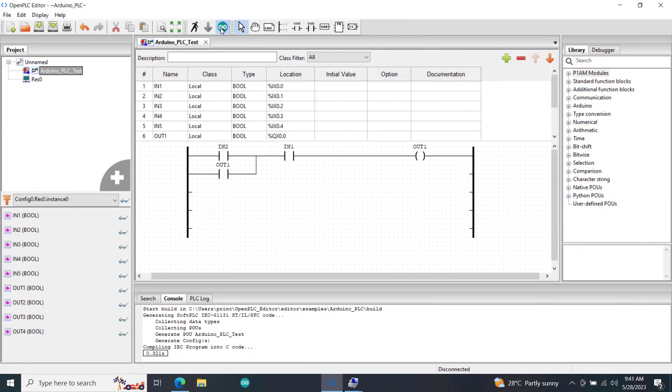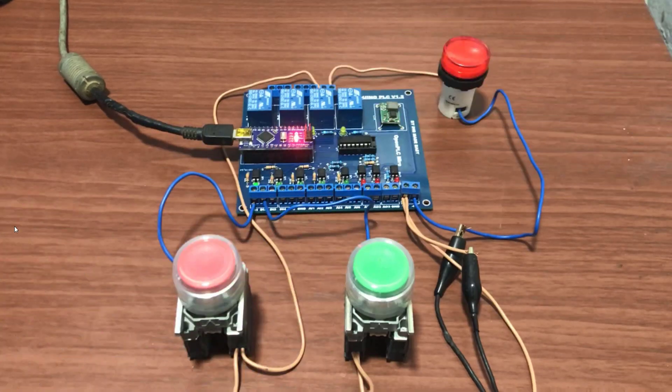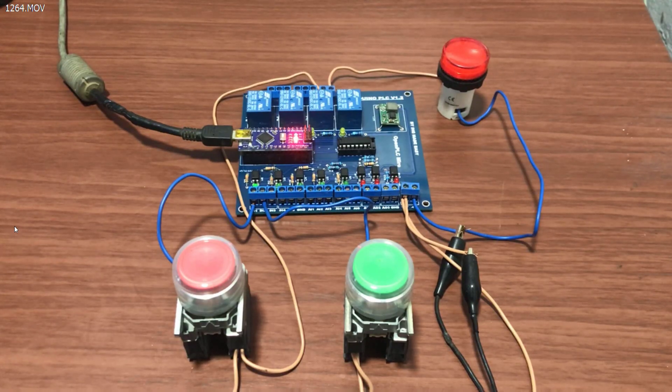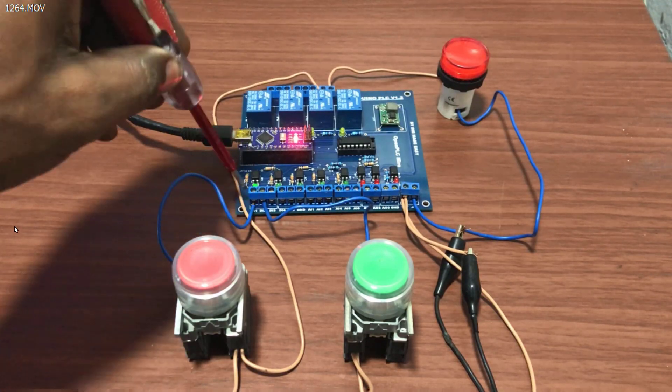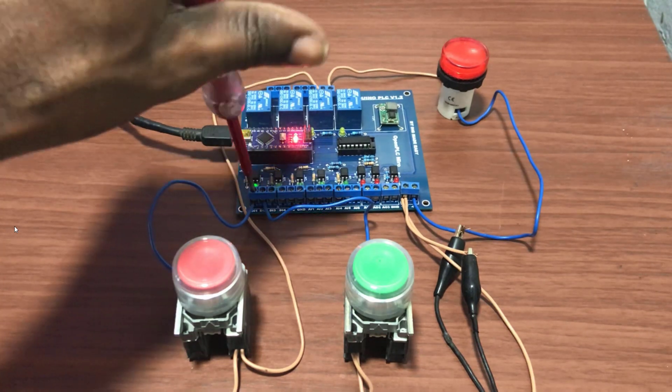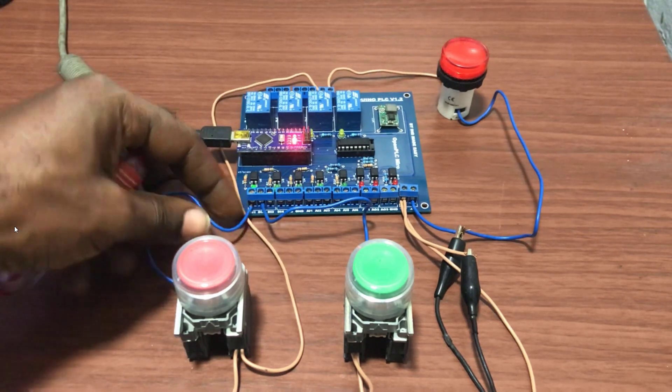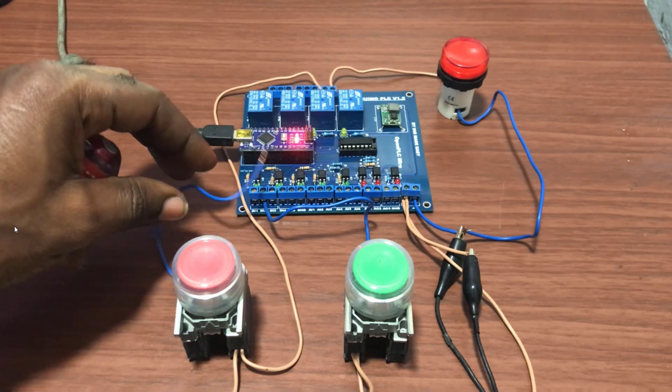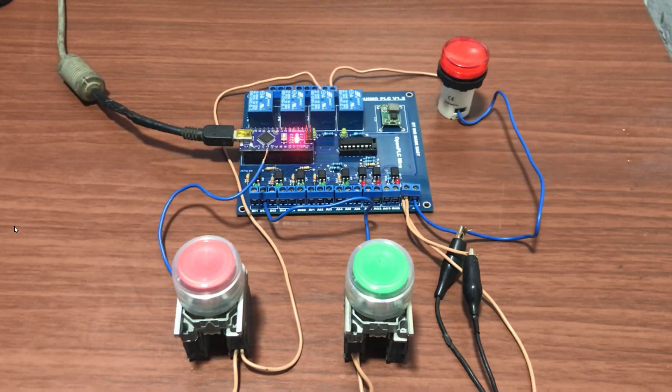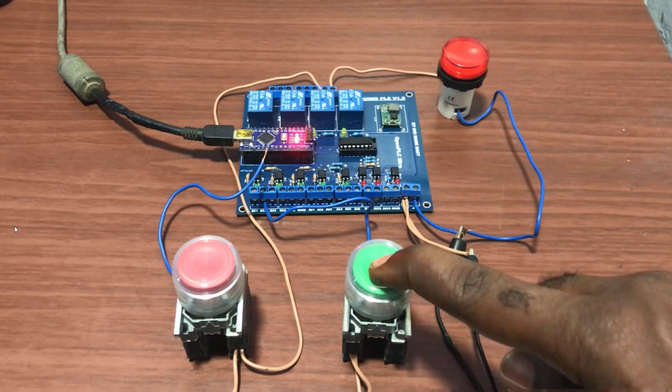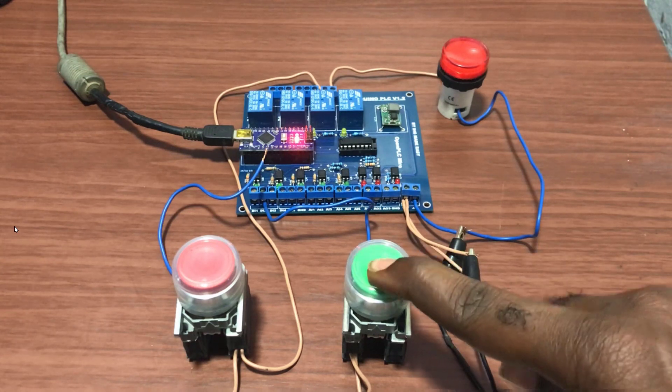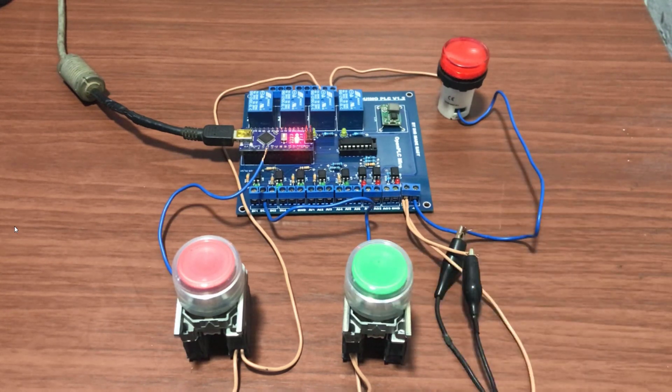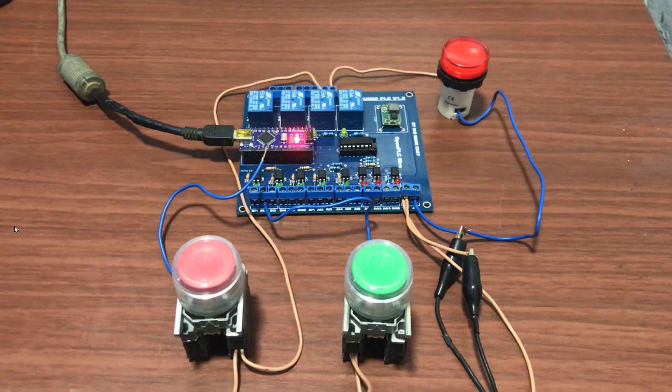We now move on and introduce a fault into this circuit and let's see how it handles this fault. So I move on with the help of a screwdriver, take off the stop cable. Let's say there's a break in the stop cable. And then you can see that when I press the start the machine does not start at all. The lamp does not come on, which means it has failed in the safe mode.